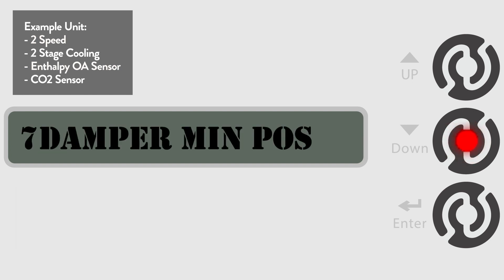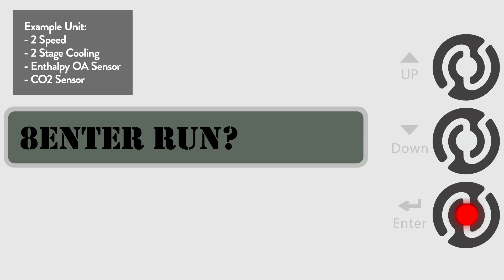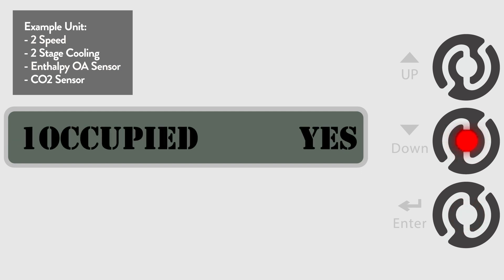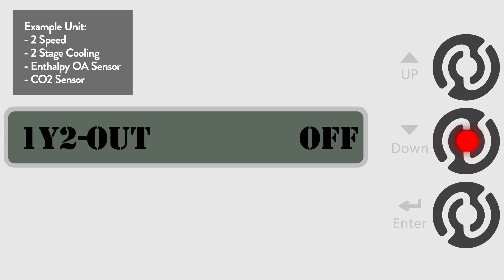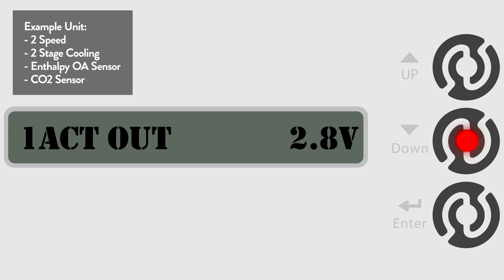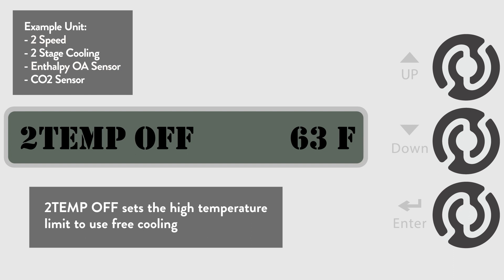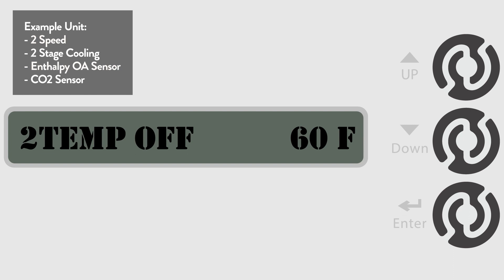Now we are going to go on to the controller's 8 run state menu. We are using temperature and humidity for the outside air sensor, so first let's go to the 2TEMP off menu. This sets the high temperature limit where the economizer free cooling is locked out. The default is 63 degrees, but let's change it to 60 degrees for this example. In the 5 configuration state menu, we selected the temperature and humidity or enthalpy outside air sensor, so now we will adjust the humidity setpoint.